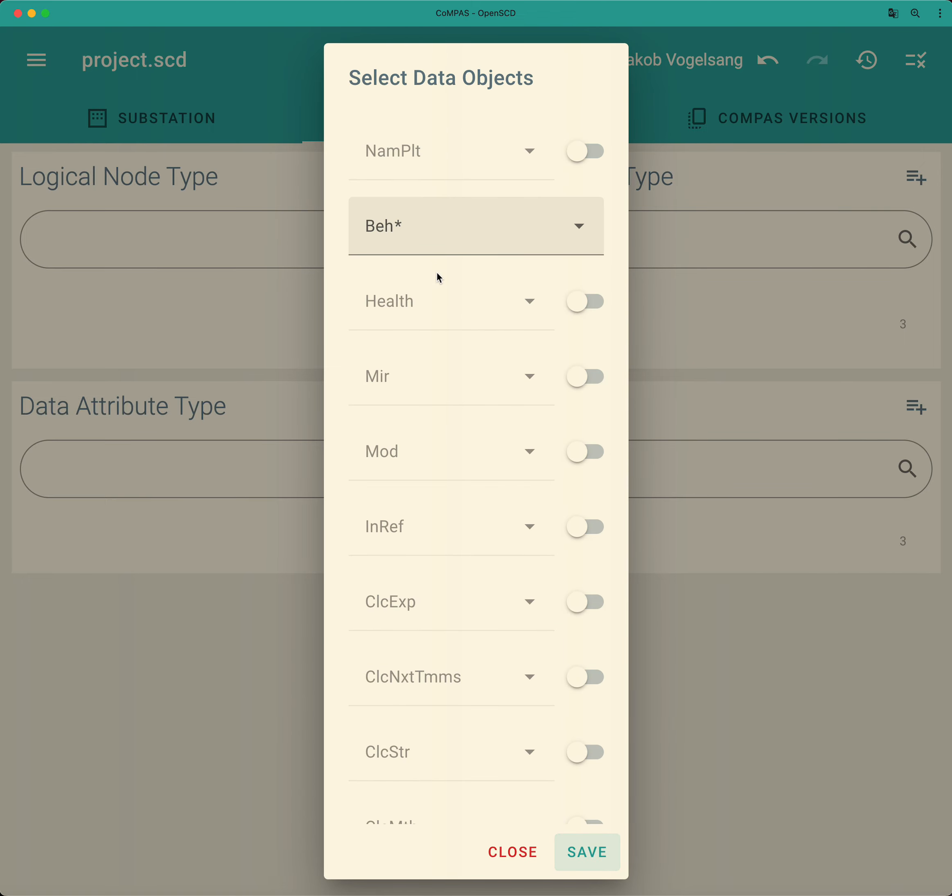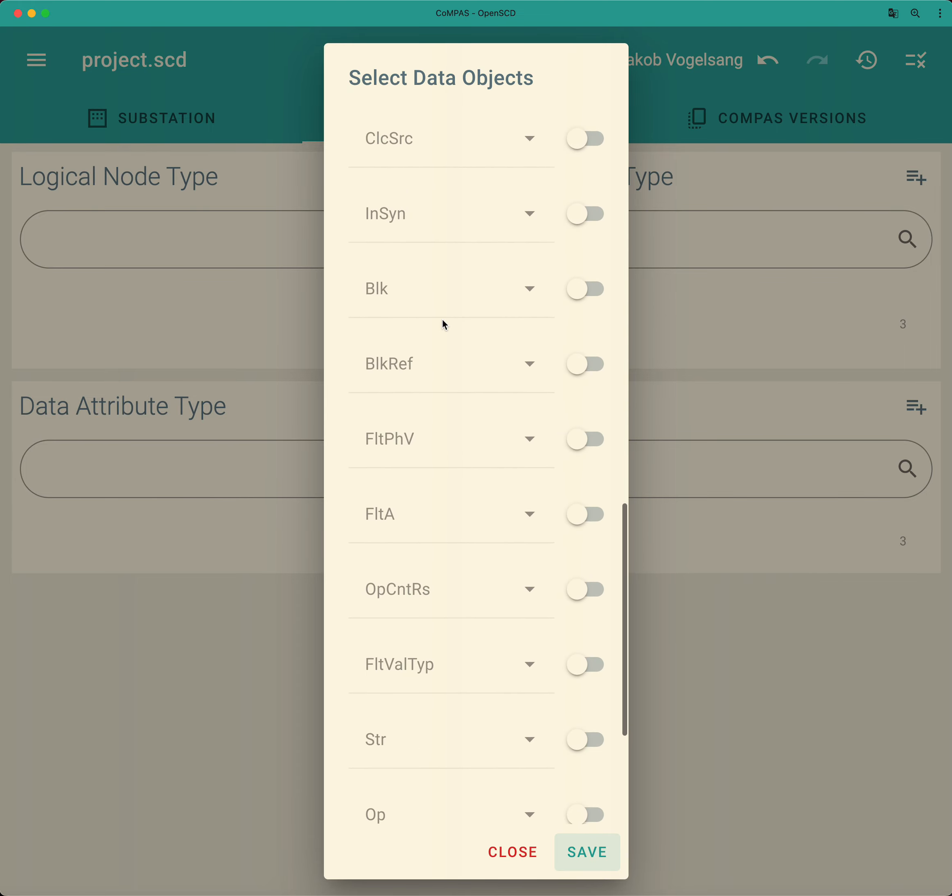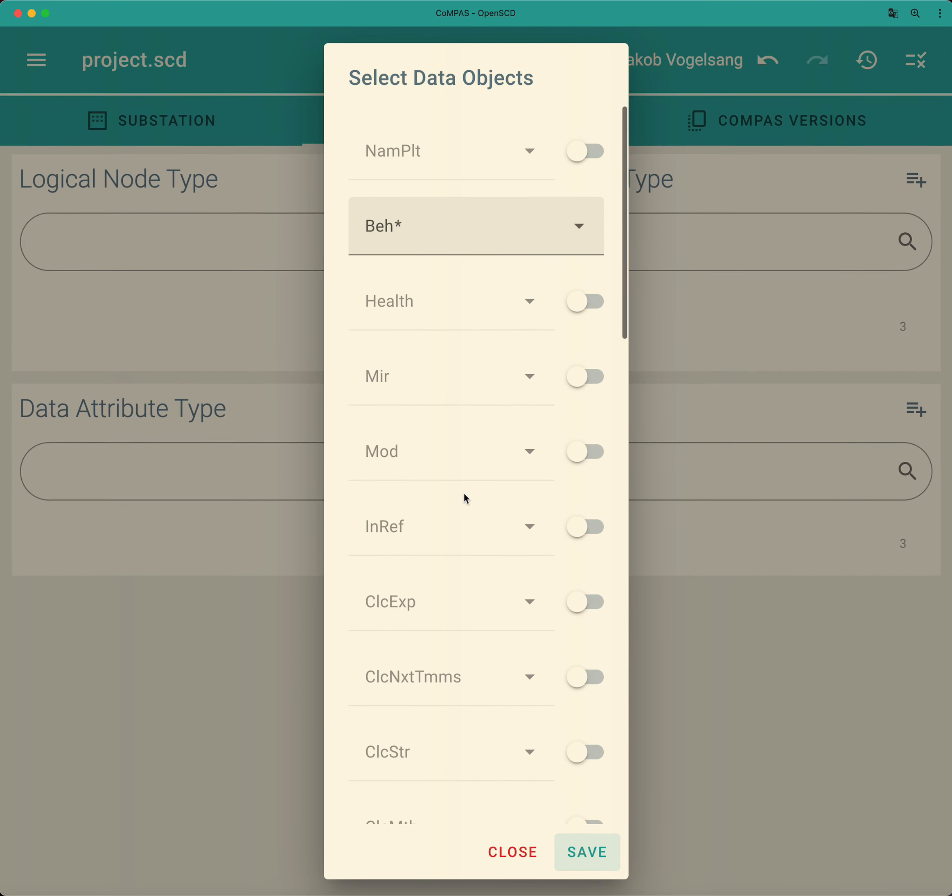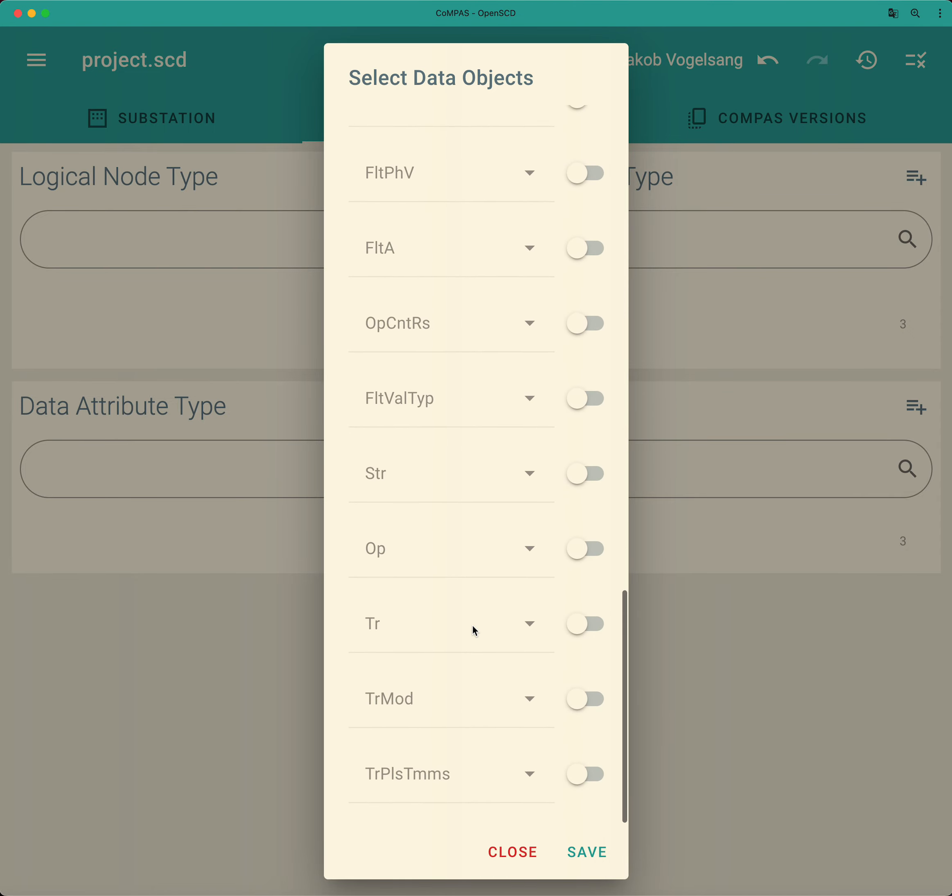Here you also backed up a little bit by the NSD files. And those tell you which data objects you can add from the namespace of the IEC 61850 and which one of those is mandatory. As I said already, the PTRC is very simple because it only needs to have a behavior data object that we just defined and can be useful.